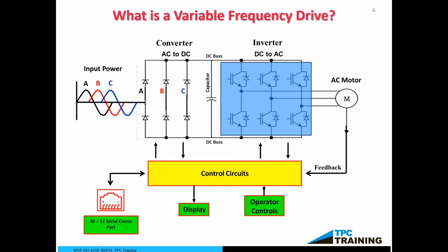There on the right-hand side, the operator controls. So whether you're operating it from an external source, whether it be push buttons for a conveyor, or maybe limit switches for a water tank to start, stop, or control this particular drive. So you can see just from the one slide right here, we've got AC coming in, converts it to DC, and that DC bus, I might add, is always going to be higher. It's 240 volts, and it's going to be 300 and something volts. If it's 480 volts, it's going to be 678 or whatever the calculated value is.